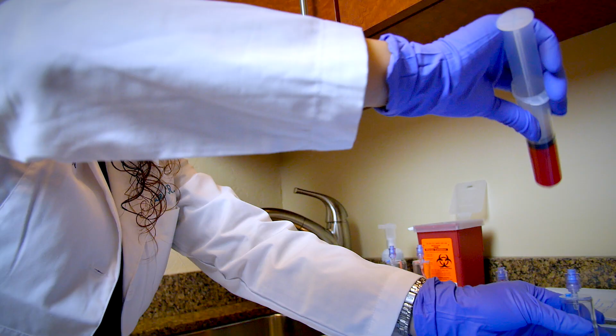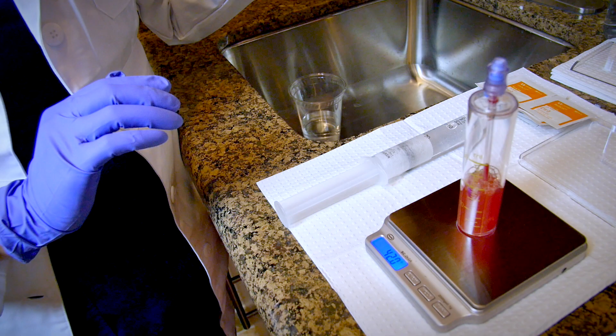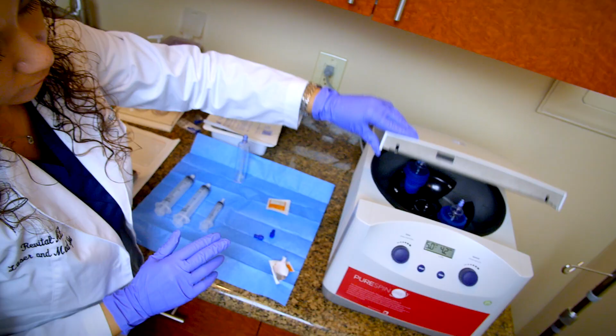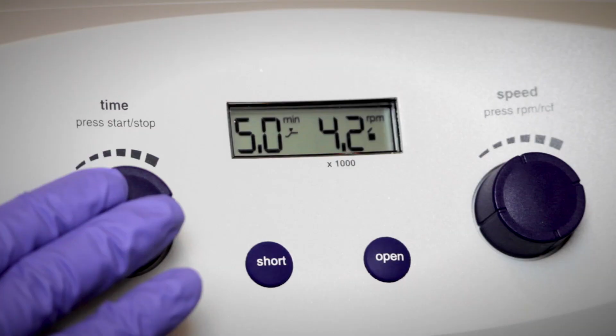Transfer the platelet plasma suspension into the concentrating accessory. Weigh the syringe and counterbalance with the provided counterbalance accessory device, and place back into the centrifuge buckets at opposite ends. Set the centrifuge at 5 minutes and 4,200 RPMs. Close the lid and press start.